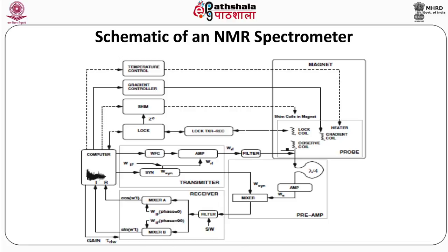On the top right corner you see a magnet in which a probe is inserted. At the bottom of the probe you see a box labeled as pre-amplifier, and then you have other boxes labeled as transmitter and receiver. The console has the electronics that generates the pulse of required radio frequency. The sample is inserted into the probe and the radio frequency pulse is applied. The signal generated by the sample is observed by the observe coil and is immediately pre-amplified, with the pre-amplifier being very close to the probe. That signal is then reduced and goes to a mixer and then through other circuits before it is digitized and stored in memory.